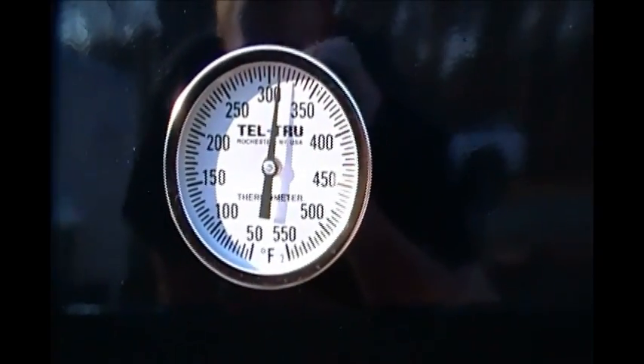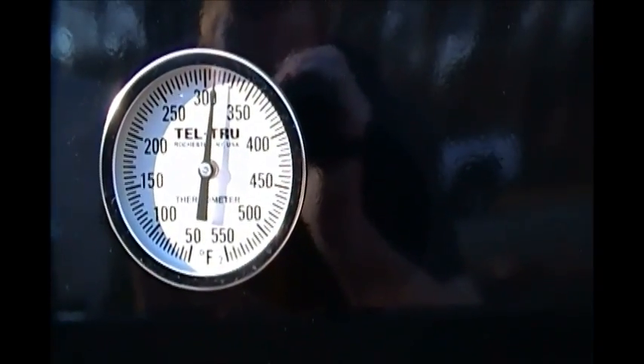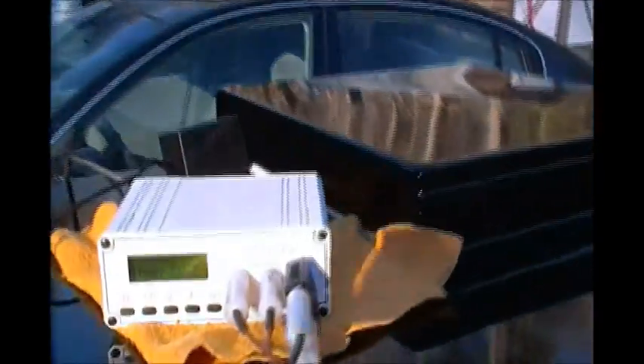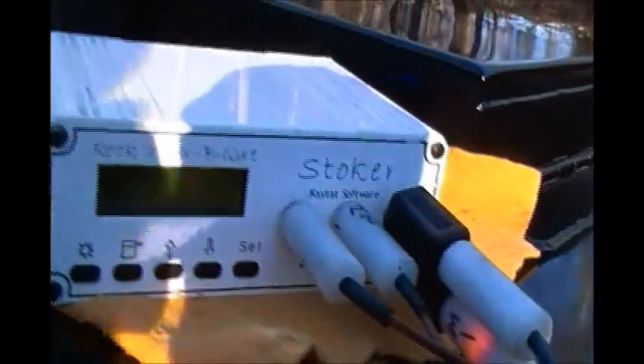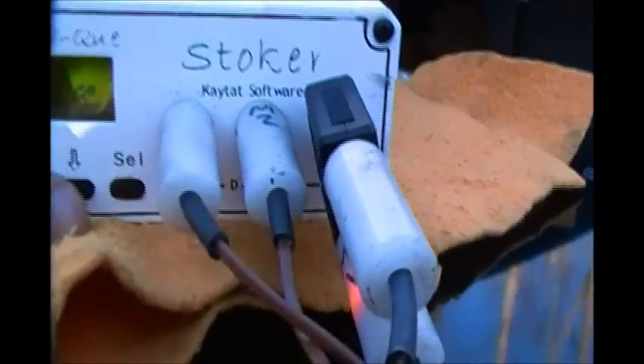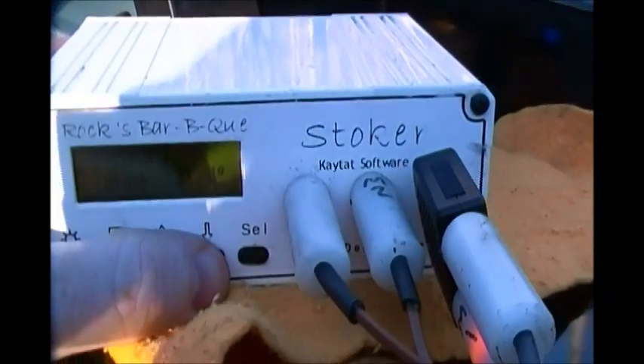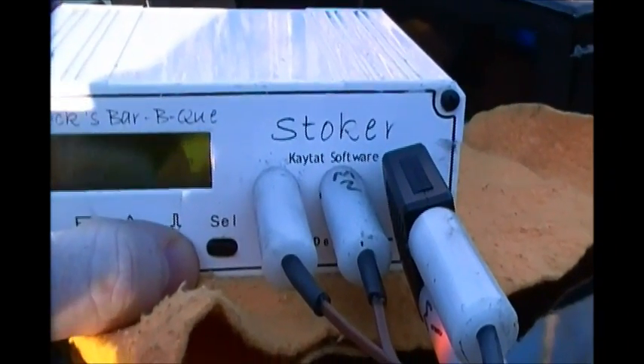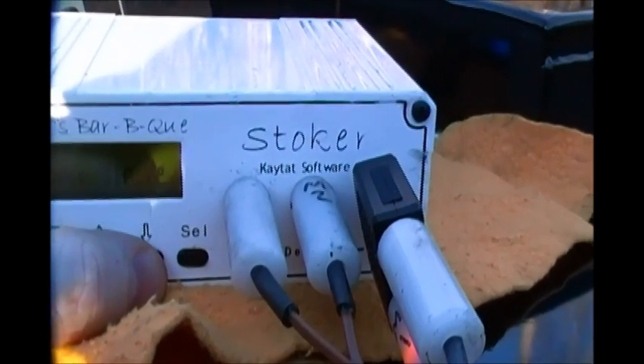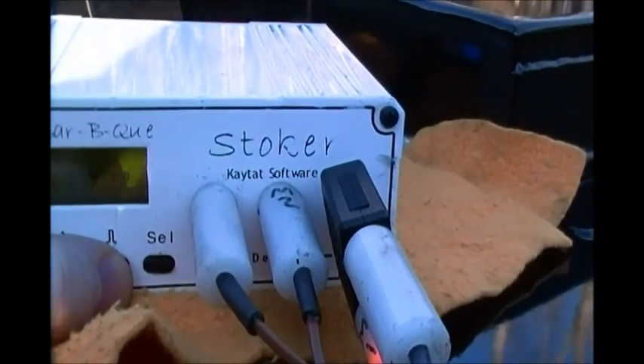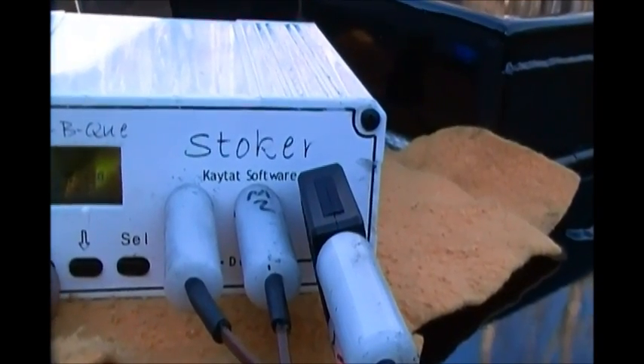Now we've got the temperature rolling at about 325. As you can see on the Tel-Tru, we're reading about 312, 313. Let's come over to the Stoker and take a look — got one sensor at 321, one at 310, one at 323.